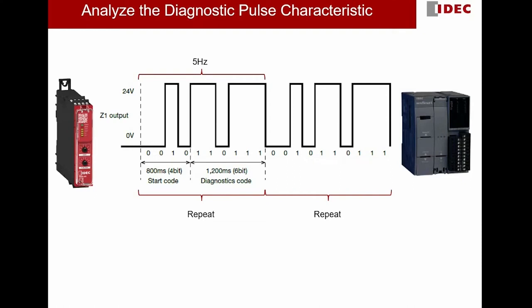One last important characteristic of this diagnostic pulse is the pulse width. The pulse width of the diagnostic pulse coming out from Z-1 terminal is actually 200 ms. If 10 bits require 2 seconds, then 2 seconds divided by 10 bits means 1 bit is 200 ms. This is very important because later on we will do sampling at the middle of the pulse width.